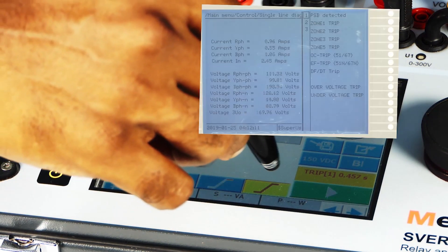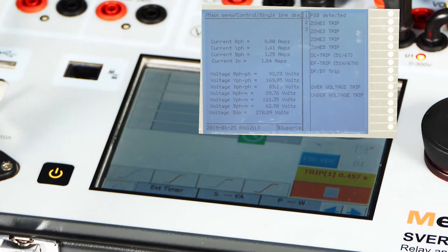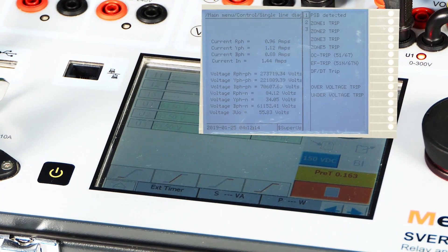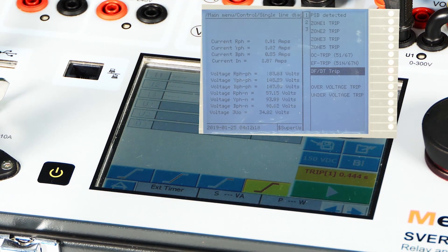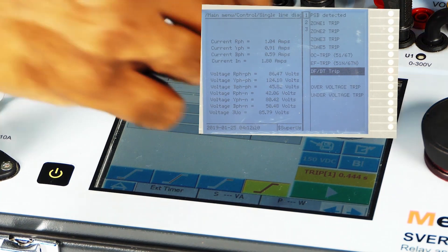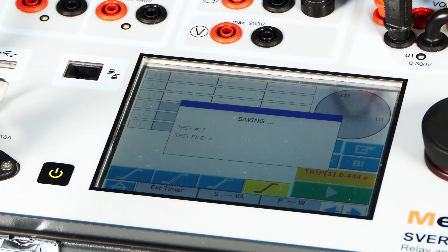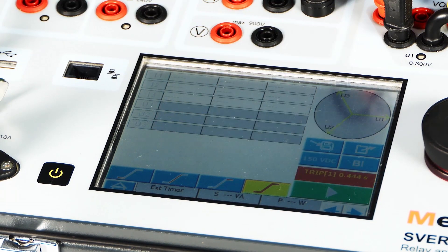Now by pressing the fourth tab, let me inject and verify the operation of the relay. The relay has successfully operated on DF per DT and the results can be saved and the reports can be viewed.